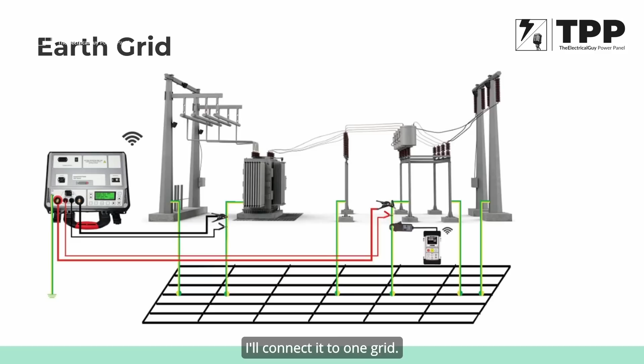Yes. Typically what happens is, let's take a simple building within the substation fence, or a power transformer or power circuit breaker. The guides recommend that you connect the opposite legs of those frames to the nearest grounding point. That could be a grid, a ground rod, or a ground well. As simple as that.